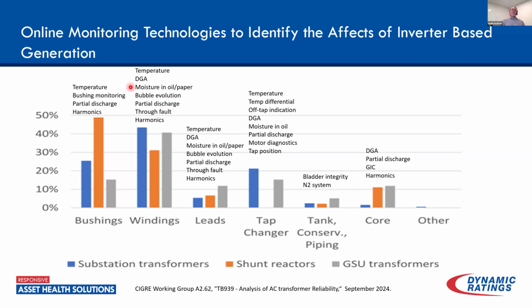Moisture in paper, we talked about that: the expansion and contraction that we're seeing due to the thermal cycling can result in increased moisture ingress. As I have increased moisture ingress, the risk due to bubble evolution increases as well. So it's good to monitor not only the moisture in paper, but also the thermal elements, to identify if we're loading the transformer in such a way that we could be driving that moisture out and possibly creating bubbles in the oil, which could result in a dielectric failure. Of course, partial discharge for the main tank is significant, we spoke about the benefits of that before.